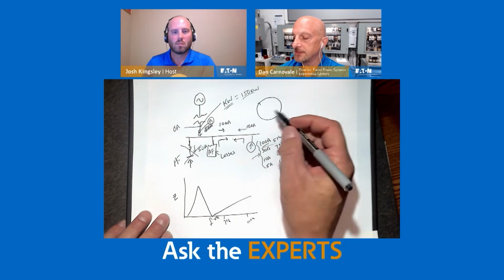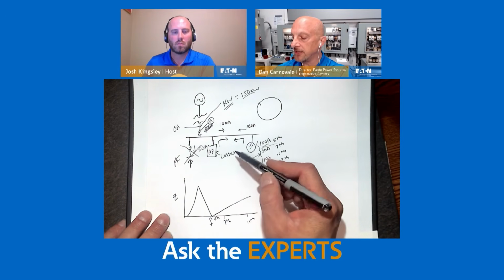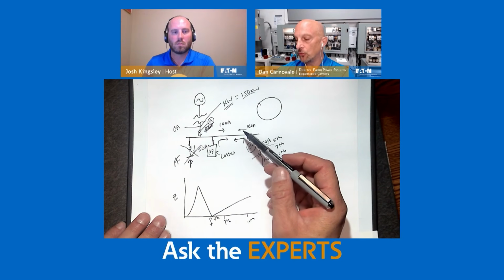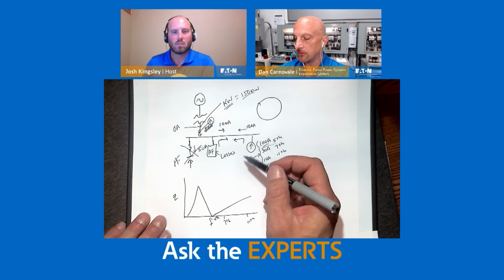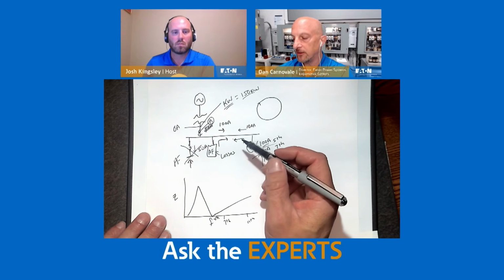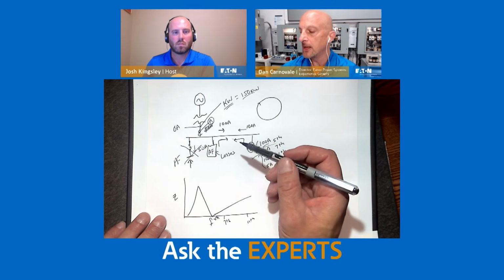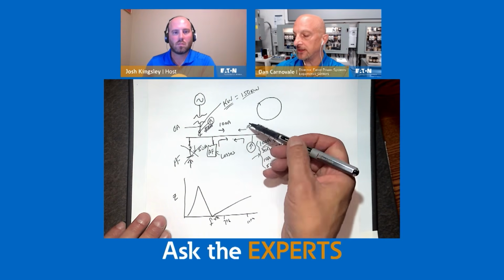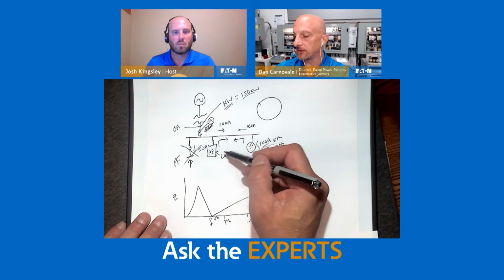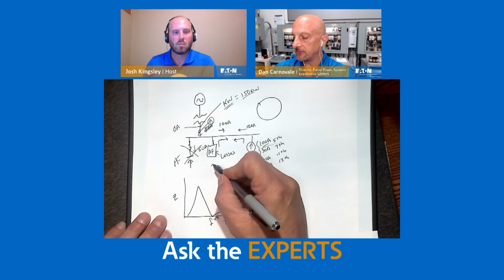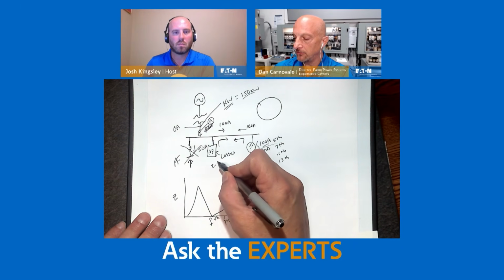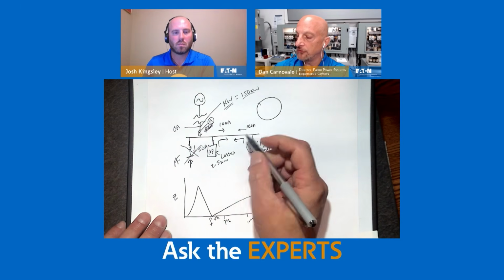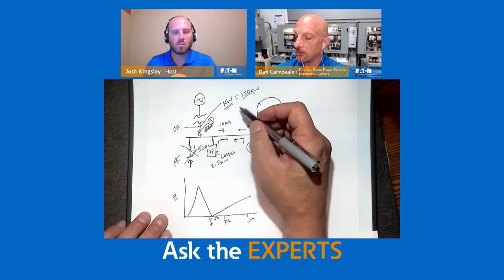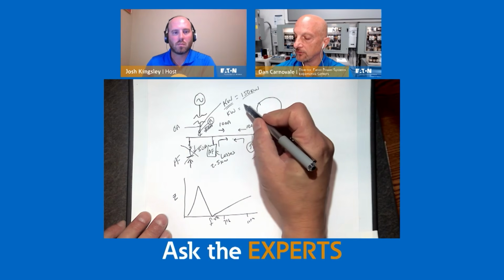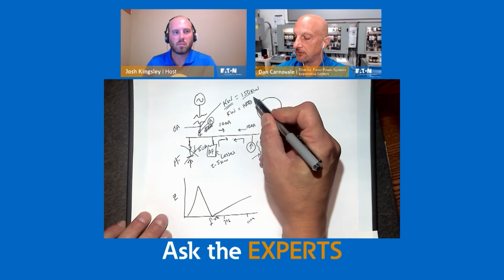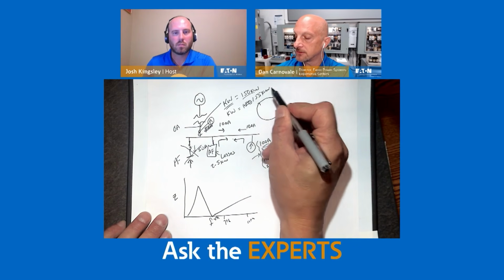And the reason they go up a little bit is because the current that you're taking out of here is not really real power, like kilowatts. It's similar to reactive power in the sense that it's distortion power. And as that current is going through the system and getting corrected by this one, this actually might have, let's say, 2 to 5 kilowatts of losses. So the power that I measure on my system with that active filter on is, say, 155 kilowatts.